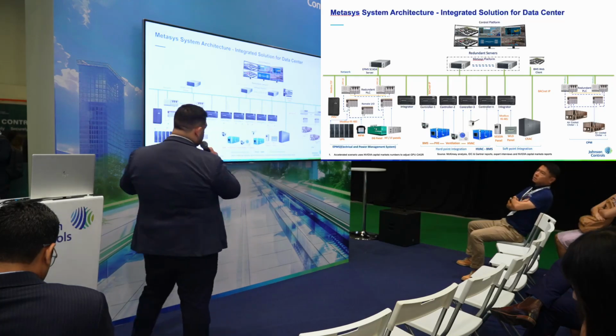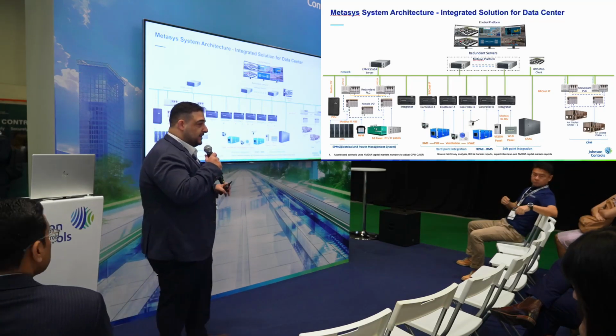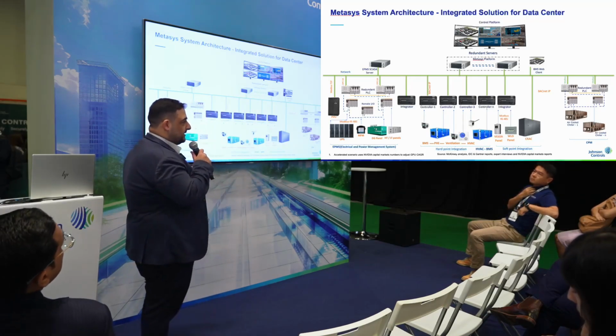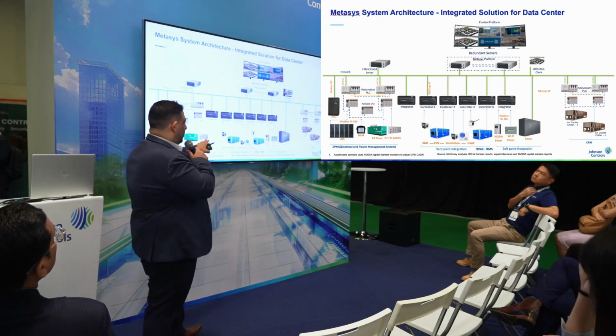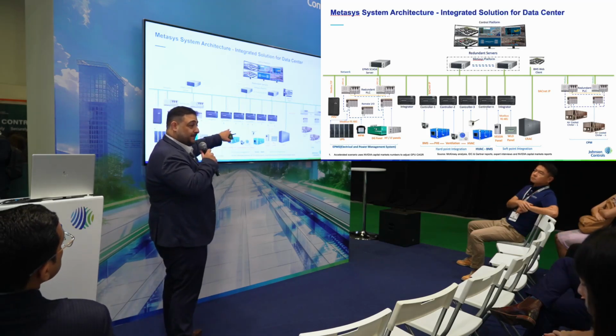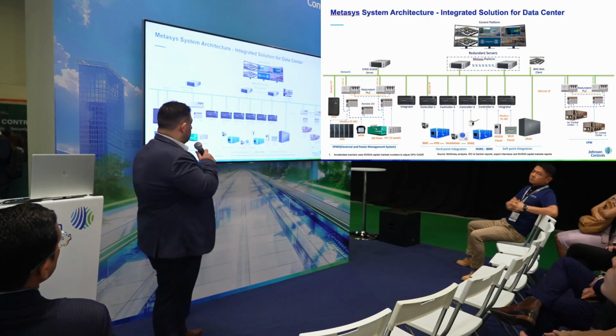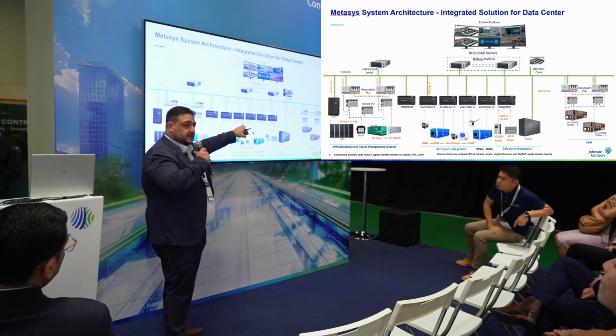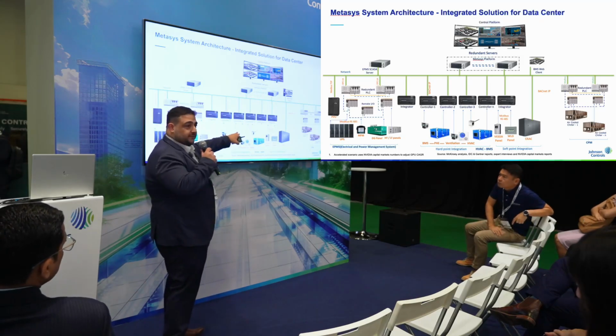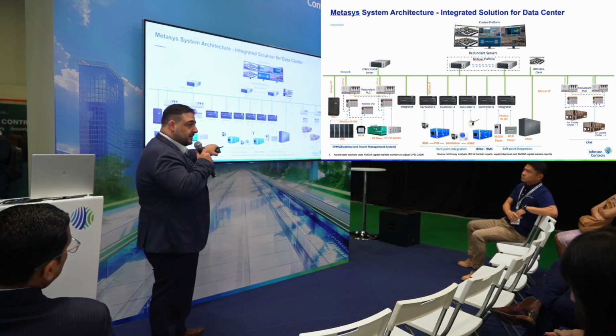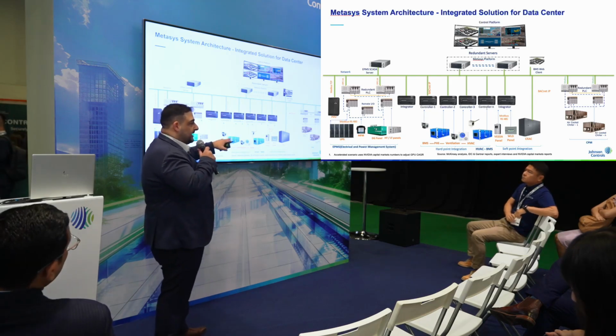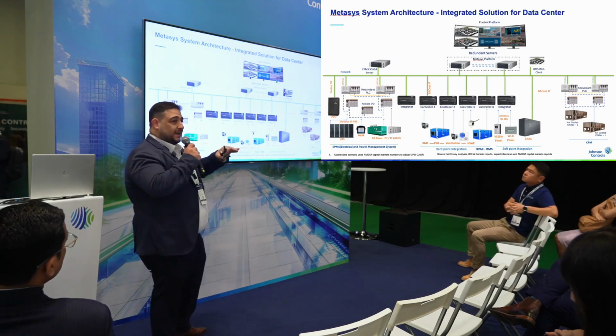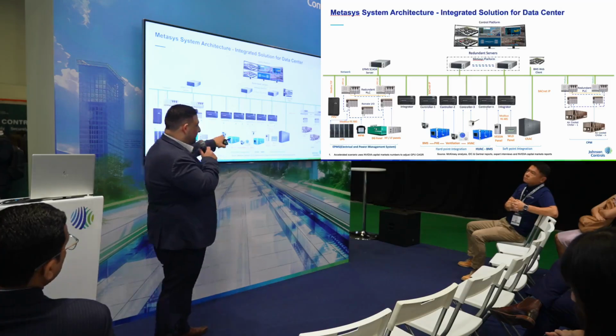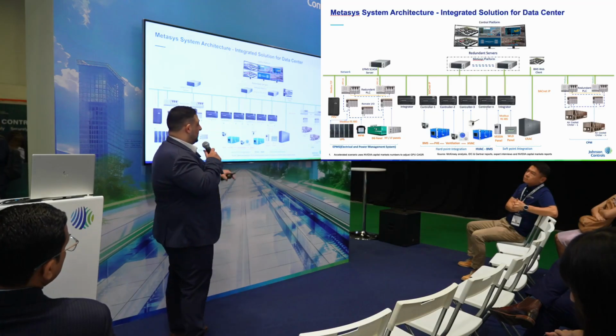I know this slide is a little noisy, but what I want to point out is where we're really known from our domain experience around Metasys. This is purely Metasys, DDC level controllers, non-critical infrastructure, because inherently air handling units or airside are N+1 design from a mechanical perspective, so you don't need that resiliency at the field level.